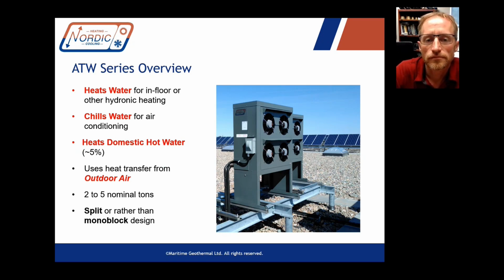So yeah, you are rejecting heat to the outside, but instead of rejecting it all, you're just diverting some of that into the hot water. Exactly. Preheat. It's too bad you couldn't direct it all into the domestic water, but that's just the nature of the desuperheater. It's a standard feature, not an optional add-on or something like that. And it's simple and cost effective to have that feature. So it's a good one to have.